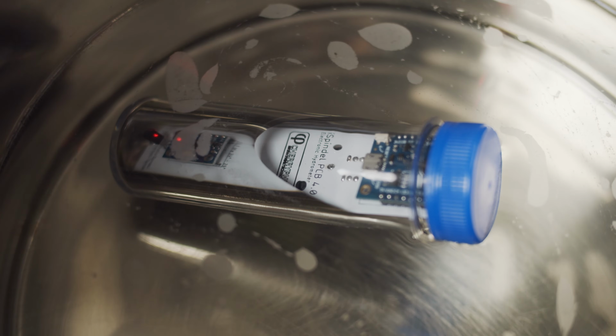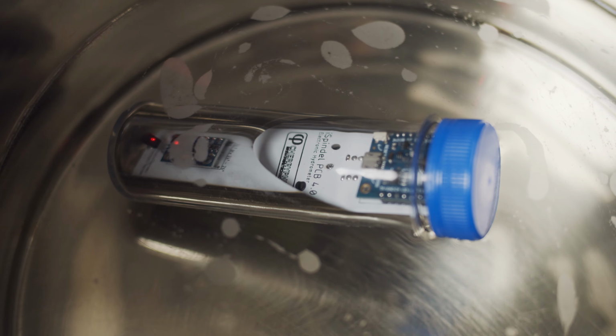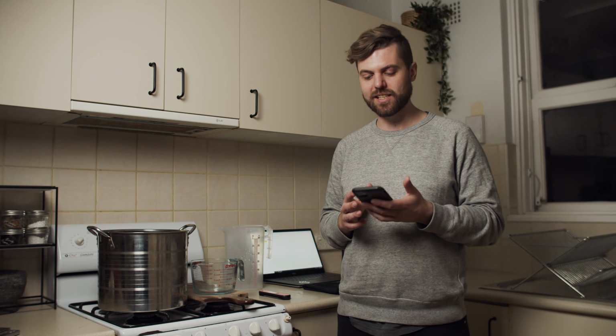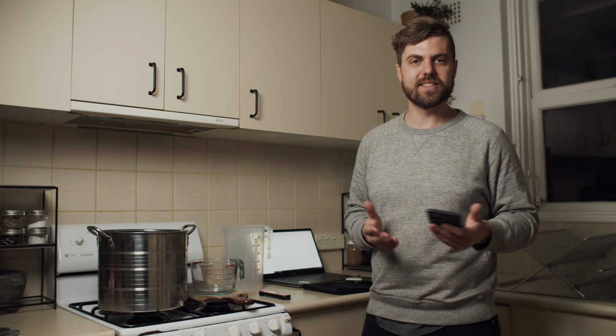All right, so the iSpindel's sitting in there, and just looking at it, you can see there's a massive difference in the way that it's sitting, and it gives you a bit of an insight into how the device actually works. Now, my tilt's reporting here just above 70, so I've got 70.08, 70.04, 70.11, 70.03, so what I'm going to call it is about 70.07, something in the middle there.